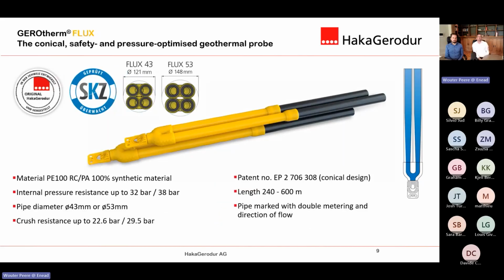So we come to the next probe. This is the Flux probe. We say it's from 240 meter to 600 meter. The standard one is up to 500 meter. We have it available in two different pipe diameters: 43 millimeter and 53 millimeter. The 53 millimeter is for deeper boreholes, and the pressure rating is 32 or 38 bar, depending on which product you choose.